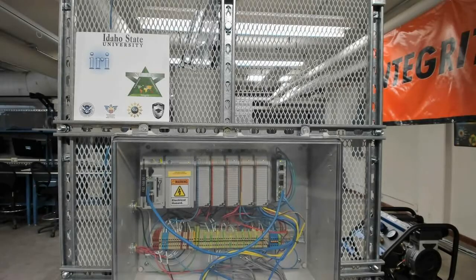On the other end of the skid is where we have our programmable logic controller. This is the brains of the skid. The programming code lives inside the processor, and here you can see that we have a network card. So we have a human-machine interface that we need to be able to communicate with an Ethernet cable. And then down here along this bus we have all of our instruments and control signals that come in and out through here. These are the different cards, and when we say cards, you can have digital or analog type cards that you add onto your PLC to be able to interface with your peripheral equipment.